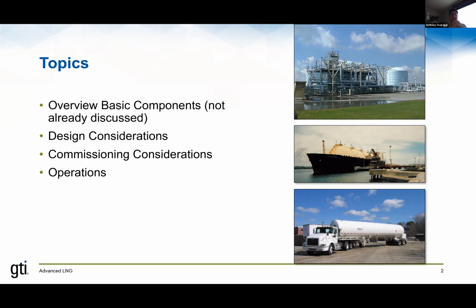Also a reminder, just like natural gas, liquefied natural gas is made up of several different components. And when we talk about the specific properties of LNG, we're really giving a number that's kind of like an average, because each of those different components within LNG can be in different concentrations, and those different concentrations lead to different total mixtures, and each of those total mixtures can have slightly different properties than other compositions, causing LNG to have a range of properties. So once again, when you hear somebody talk about something like the temperature of LNG being minus 260 degrees, if you hear somebody else say minus 258 or so, neither is wrong. The actual properties are in a given range.